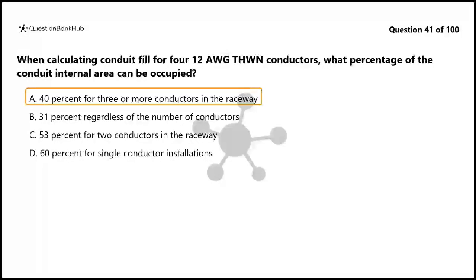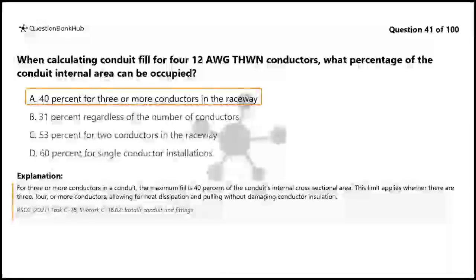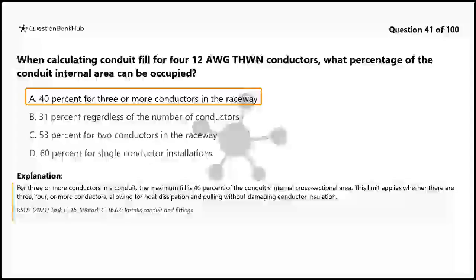The correct answer is A, 40% for 3 or more conductors in the raceway. For 3 or more conductors in a conduit, the maximum fill is 40% of the conduit's internal cross-sectional area. This limit applies whether there are 3, 4, or more conductors, allowing for heat dissipation and pulling without damaging conductor insulation.